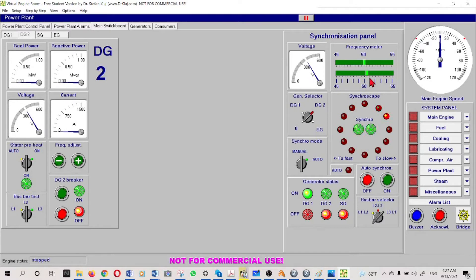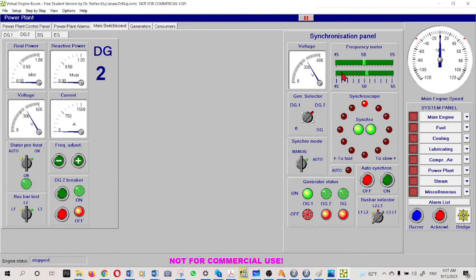The incoming generator frequency is slightly higher than 50Hz, and the synchroscope is rotating clockwise - that is the indication that the generator is running at slightly higher speed, and that means slightly high voltage and slightly high frequency. I can adjust just to see whether when the speed drops, the voltage and frequency will also drop and the synchroscope should rotate the other way. So we'll reduce the speed.